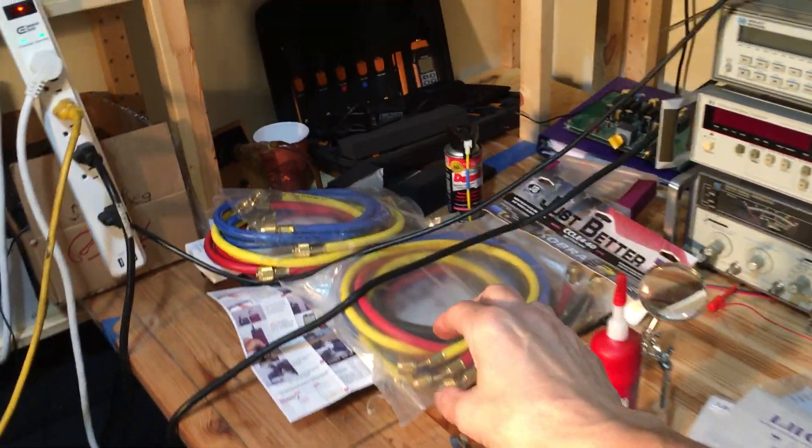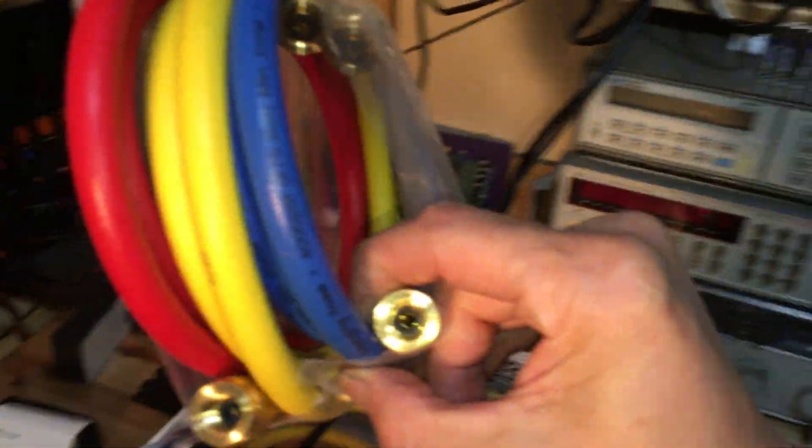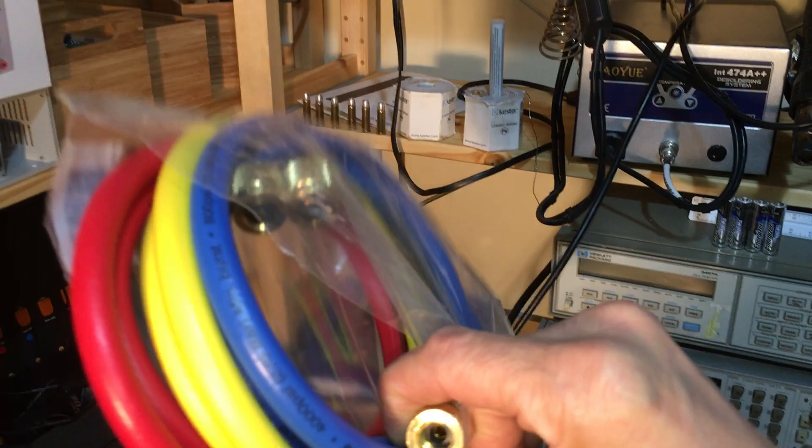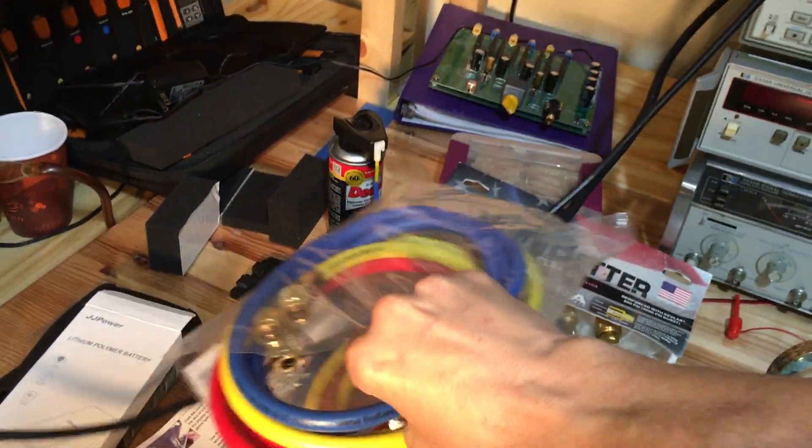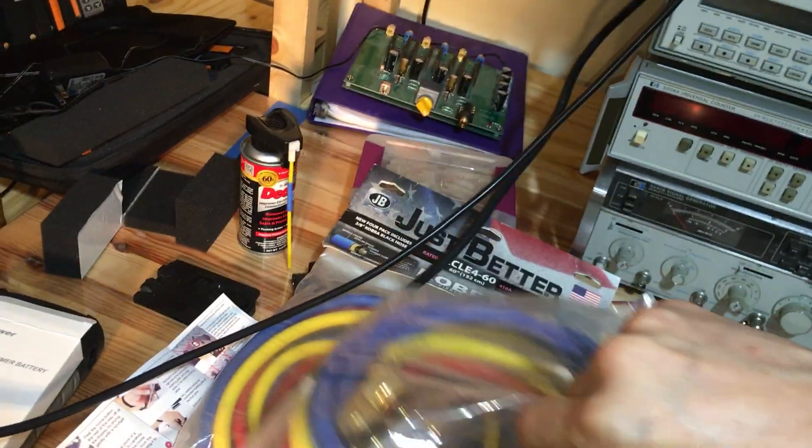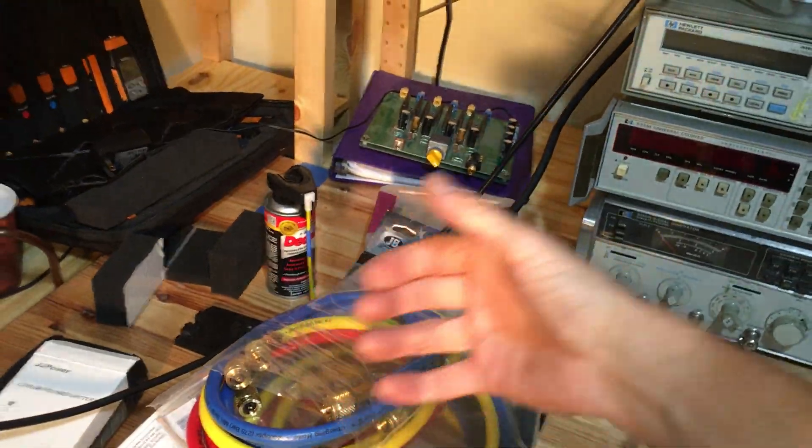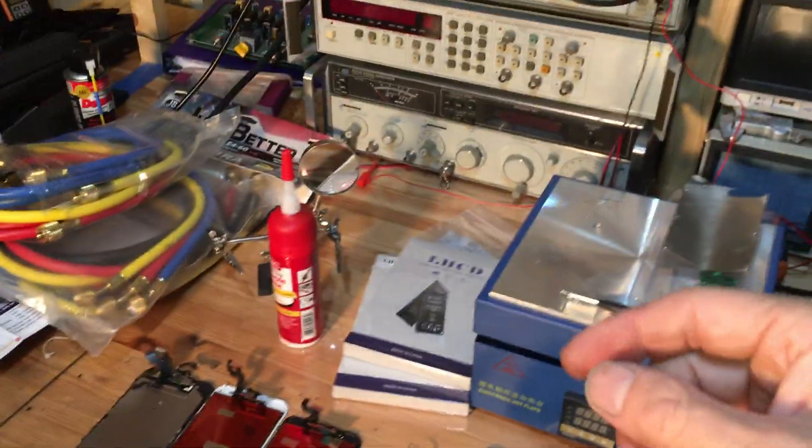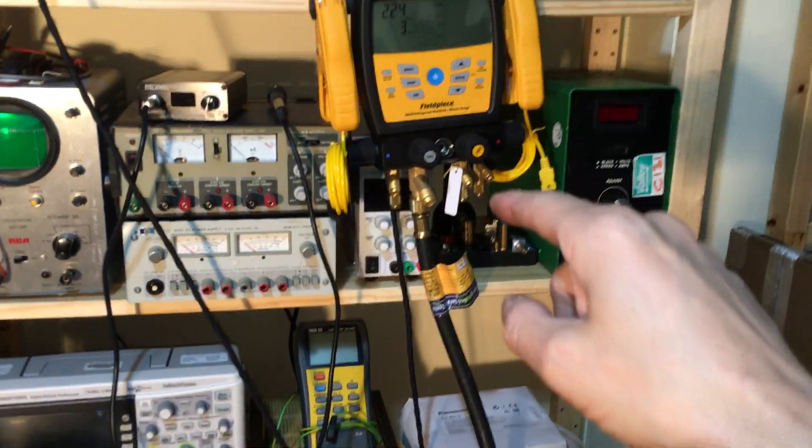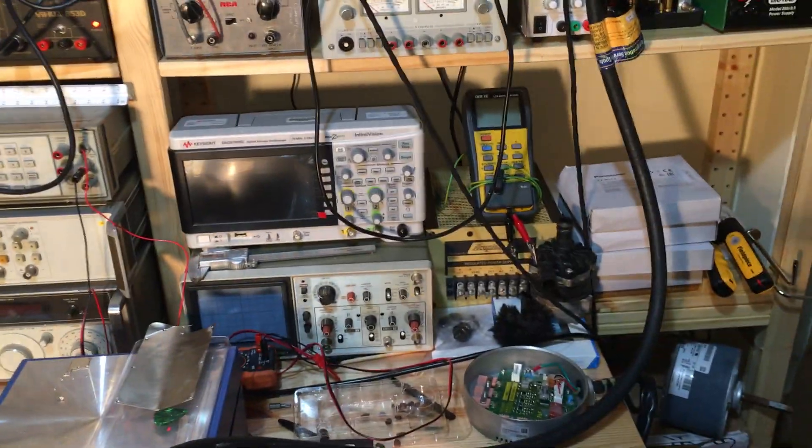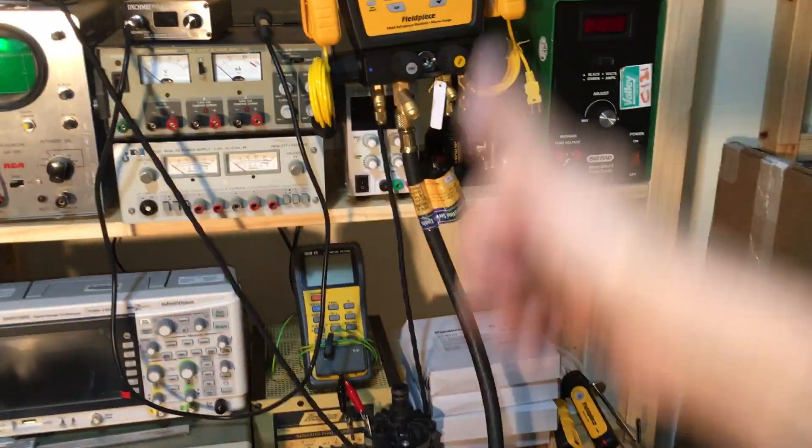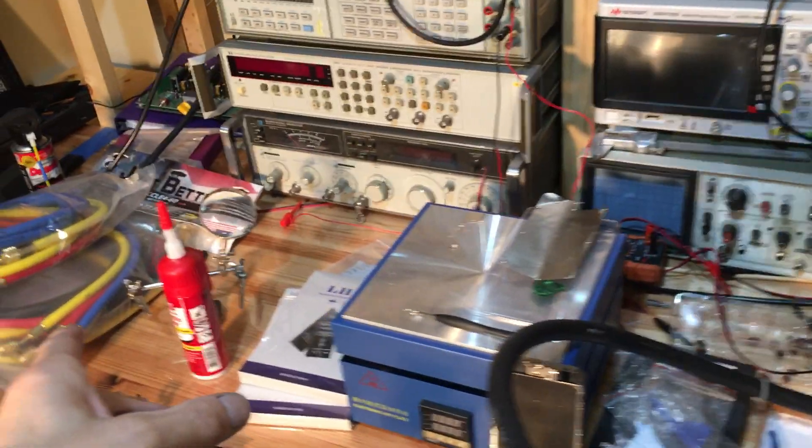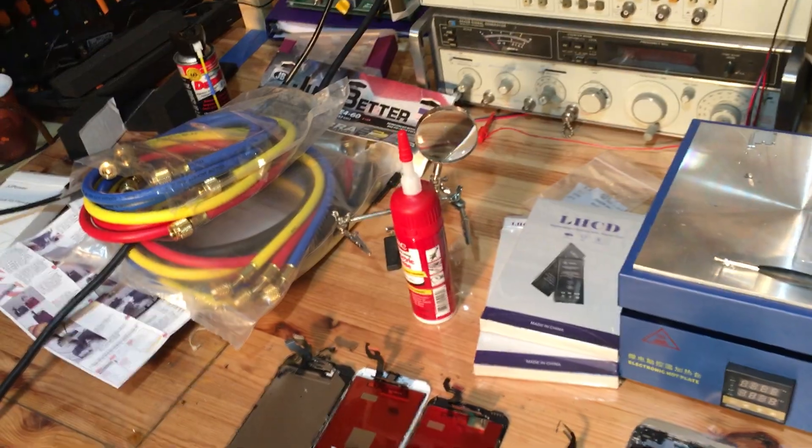The hoses are actually, the material inside the hoses are latent with moisture, sorry, these are brand new. Water has literally absorbed into the rubber material. So when you put them under a vacuum and you brought it right down to 500 microns and shut it off, you will instantly see your micron shoot right up. It's not that it has a leak essentially. It's all the water that is boiling out of your brand new hoses.